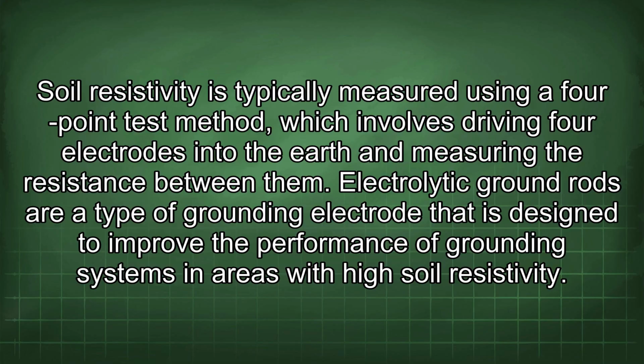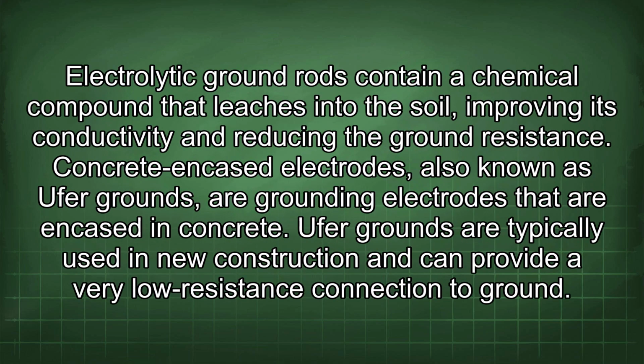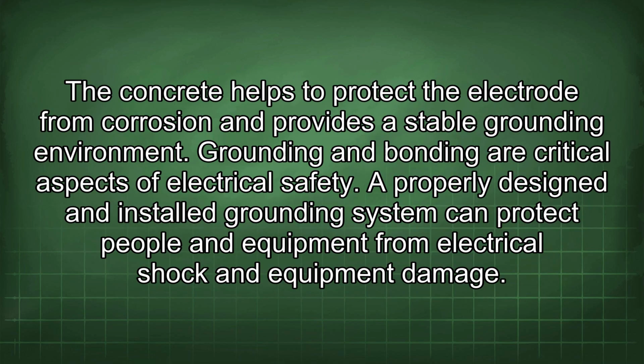Electrolytic ground rods are a type of grounding electrode that is designed to improve the performance of grounding systems in areas with high soil resistivity. Electrolytic ground rods contain a chemical compound that leaches into the soil, improving its conductivity and reducing the ground resistance. Concrete encased electrodes, also known as UFER grounds, are grounding electrodes that are encased in concrete. UFER grounds are typically used in new construction and can provide a very low resistance connection to ground. The concrete helps to protect the electrode from corrosion and provides a stable grounding environment.